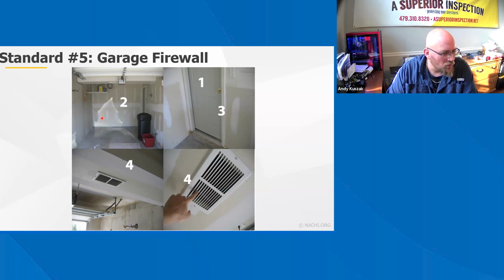Let's see, what else do we see here? Or say they put a closet for the water heater in this corner, and the drywall is not mudded or taped in that closet, and the door is not weather sealed, so they don't have a weather strip. It's not air sealed. There's no combustion venting in there. So again, even though they put a closet in there and tried to make the water heater look nice in the garage, they are still required to mud and tape the seams and the screw and nail hole penetrations.